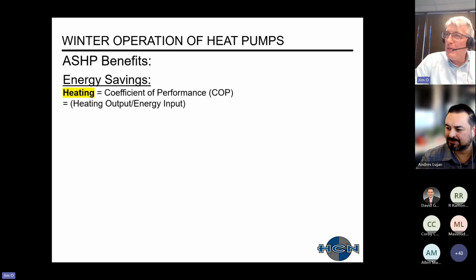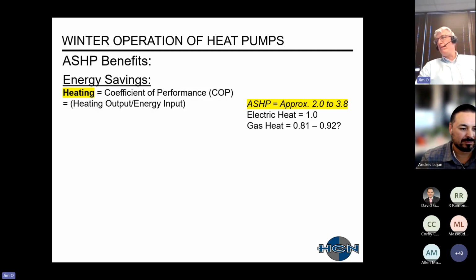All right, air source heat pumps benefit with energy savings, especially in heating mode. There's an efficiency performance measure called coefficient of performance, where basically, like any efficiency, it's how much output you're getting versus input. For this situation, it's how much heating we're getting out versus how much energy we're putting in. So an air source heat pump has a COP in a range of approximately 2 up to 3.8. As a comparison, electric heat is 1.0. And if you do have gas heat, whether your AFUE efficiency is 80%, 90, or 92, that's your range for the COP.